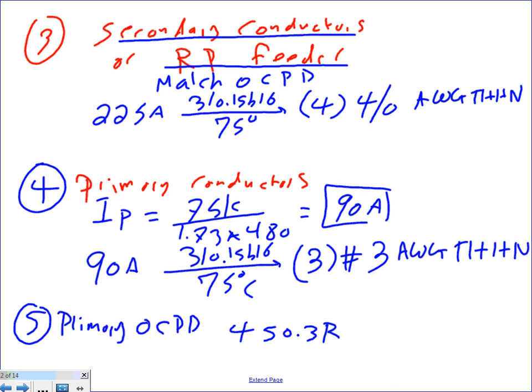It is not wrong to multiply the primary current by 1.25 and then size up, but the problem is you end up oversizing. We already jumped up to find the standard transformer size, which already accounted for the 1.25 continuous load factor, so multiplying again results in double-counting. That's why we don't multiply the primary conductor current by 1.25 in this scenario.